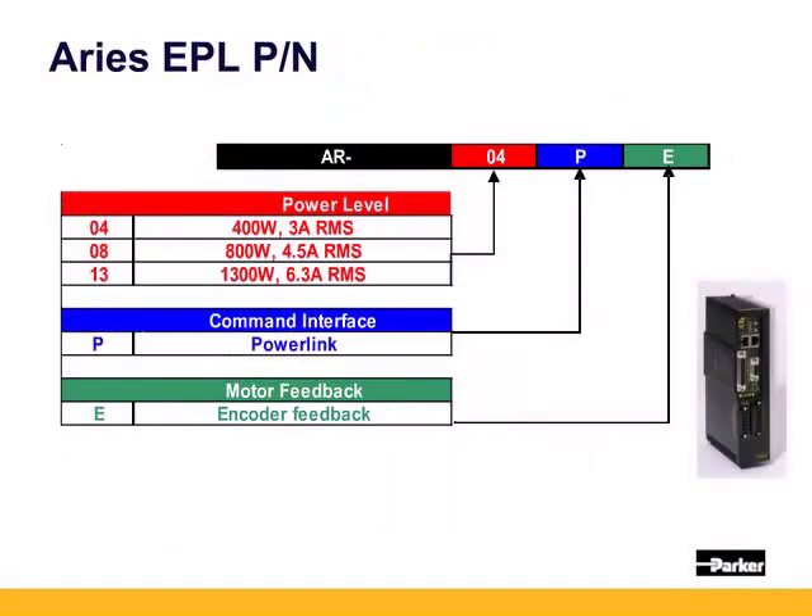For the ethernet powerlink drives, the ARIES EPL are offered currently in three power levels: 400 watts / 3 amps RMS, 800 watts / 4.5 amps, and 1300 watts / 6.3 amps. P designates ethernet powerlink, and the E variant supports incremental quadrature encoders, Heidenhain absolute EnDat encoders, and Parker's smart encoder.